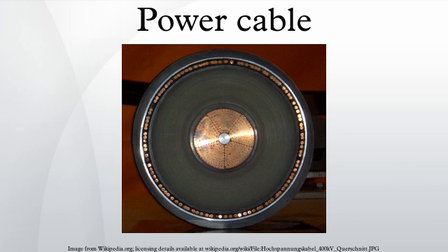The construction and material are determined by three main factors: working voltage, determining the thickness of the insulation; current carrying capacity, determining the cross-sectional size of the conductor, S; and environmental conditions such as temperature, water, chemical or sunlight exposure, and mechanical impact, determining the form and composition of the outer cable jacket.